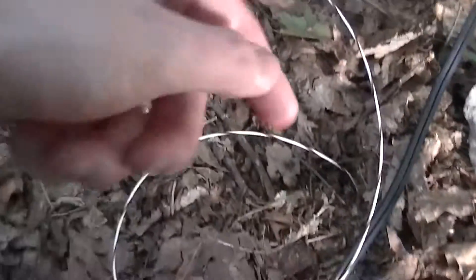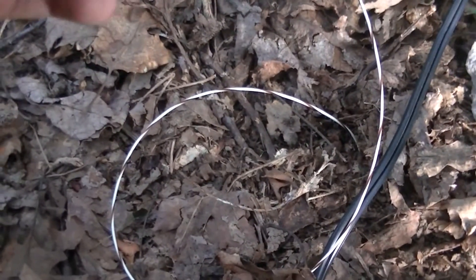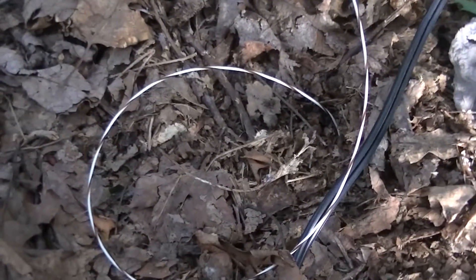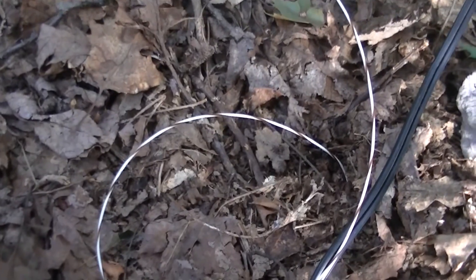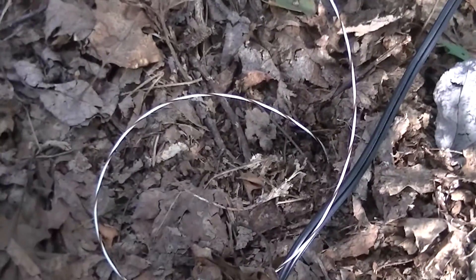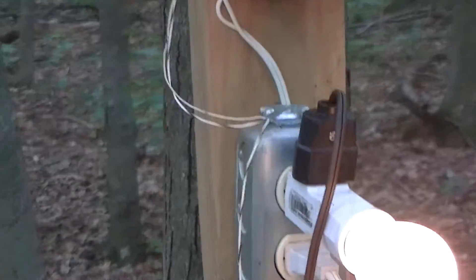That's one of the two safety grounds I have. It's very crude — just a wire with a couple inches of insulation stripped off, wrapped around a nail and jammed into the ground. I did the same thing at the other end. That's hopefully what would prevent any dangerous voltage excursions with all this equipment, if something were to happen to the safety ground or the main return.